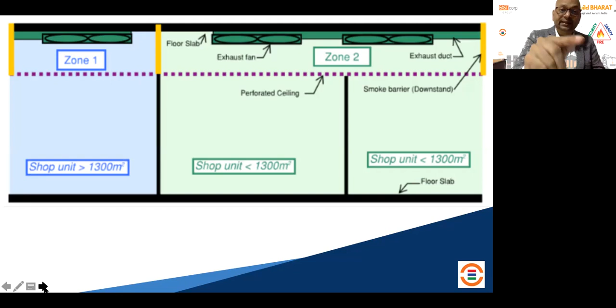So if you have a ceiling void area which is uniform, which is not partitioned from the ceiling void perspective, it is only partitioned from the room void perspective, then how do you manage the smoke? Because you still need to compartment the ceiling void area. And how do you do that? You have to do that with smoke barriers. When you have smoke barriers, it will restrict the smoke in a confined area, and then you take that smoke out through exhaust fans, and that's how you manage your smoke in the ceiling void area. So these are various techniques which are to be thoughtfully decided and engineered during your strategy.